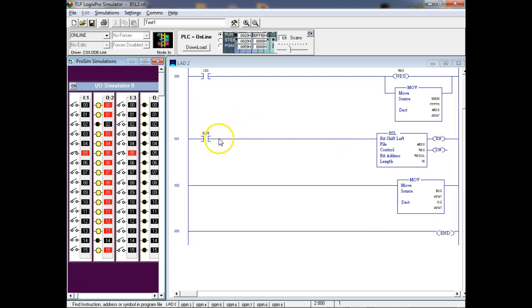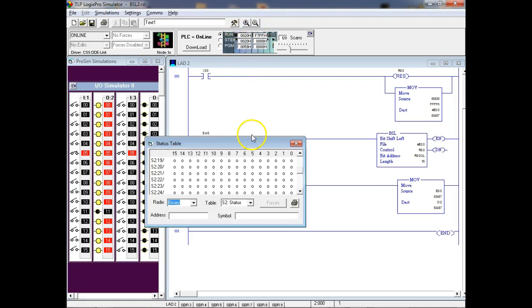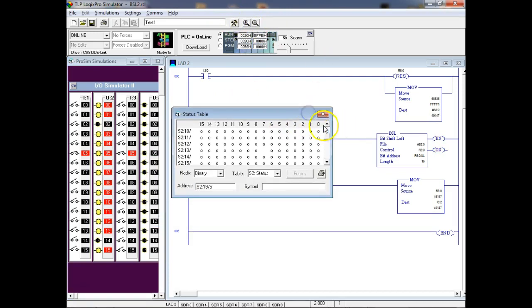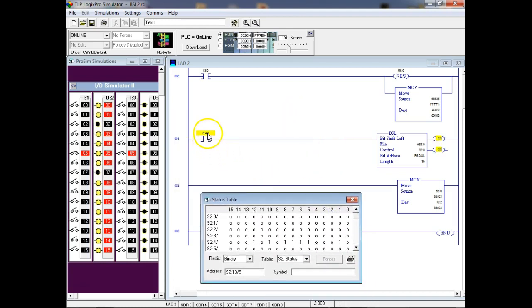By the way, what am I using for my timing? Back there in Introduction to PLCs, we could cross couple timers, right? You understand? And what we did, we used the timer timing bit and switched them back and forth and back and forth. You don't have to do that. I'm coming up here and I'm using this register right here, the free running register. And I'm using bit 5, so S word 4, bit 5. So I'm using this bit right here.